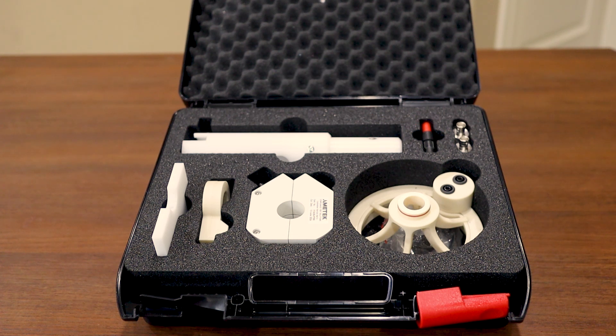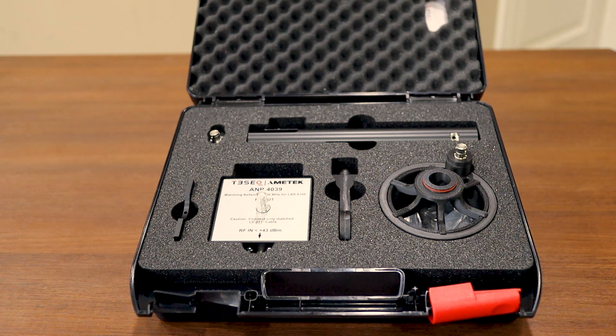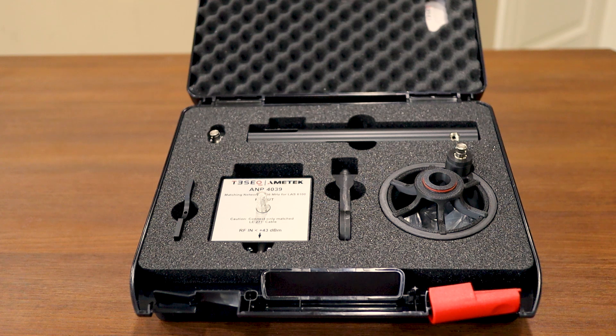Now let's take a look at the LAS6100. The LAS6100 radiating loop antenna kit and sensor has a frequency range of 150 kHz to 30 MHz, meeting the testing requirements of IEC 61000-4-39 and IEC 60601-1-2. This kit uses the RLA6100-3 radiating loop as well as the ANP4039 adapter to allow for more field strength at 13.56 MHz as required by IEC 60601-1-2. Let's walk through some of the different components that are included.